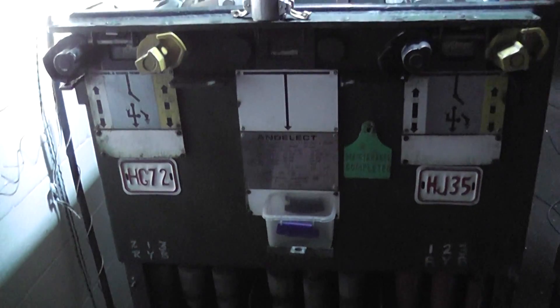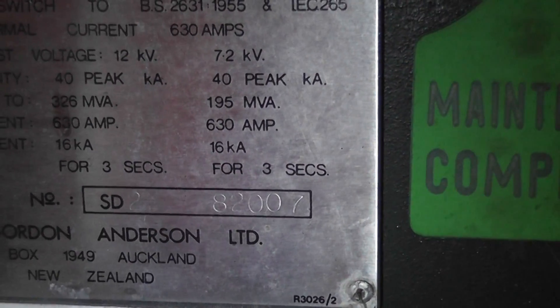The earlier ones are Series 1. SD2 is non-fused take-off. See the oil here - we just pop the lid. That's the lid. We just remove the LV fuses here. There's a new cable put in here at some stage, because that's not a PILC, so they must have had a cable fault here at some stage. The unit is in very good condition. It's a plain Jane SD2. Serial number 82007, so my guess is 1982.